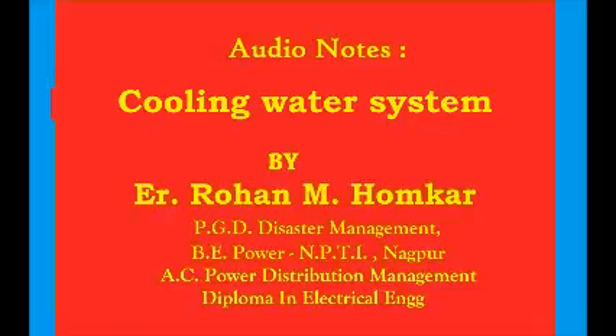The example of such a case is the Panki power project at Kanpur. For 11 months, a normal once-through system is used for condenser cooling, and for the remaining 1 month cooling towers are used when the canal runs dry. The water from the Ganga canal is pumped with the help of three pumps, each having a capacity of 80,000 cubic meters per hour.